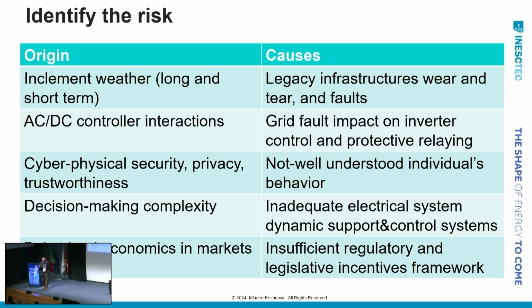Particularly when you have a disturbance, whether it's a fault or a frequency disturbance, that impacts the inverter controls, and then the inverter controls impact the relaying. And the relaying trips when it shouldn't trip, for example. If you look at the NERC reports, we had really bad cases in Texas, California, Arizona, and so on. When everything was investigated, it was not entirely clear what the problem was. Eventually the problem was traced down to bad controller designs, not good settings of the controllers, relay functions that are not adequate, and so on, all creating risk that was not anticipated or understood fully.